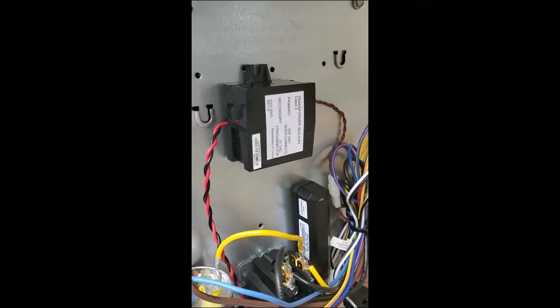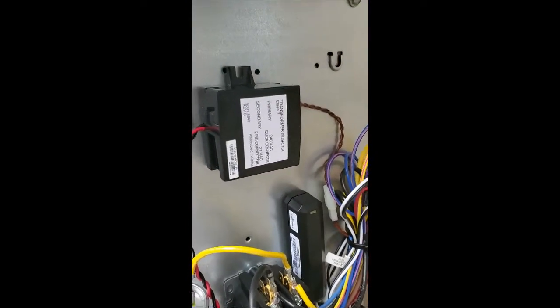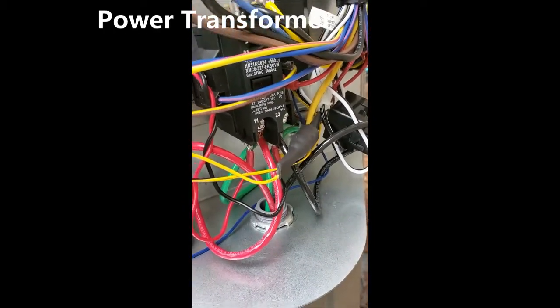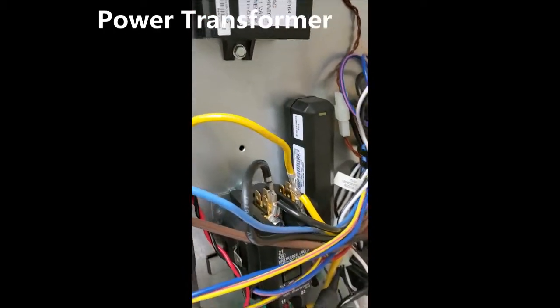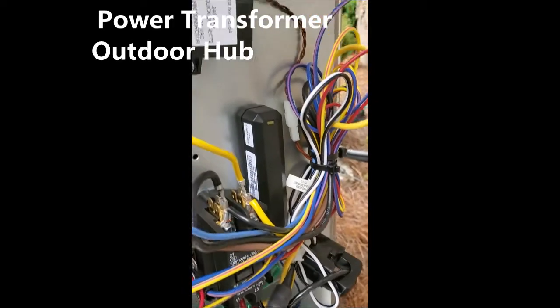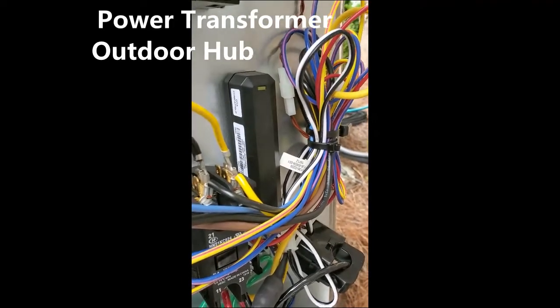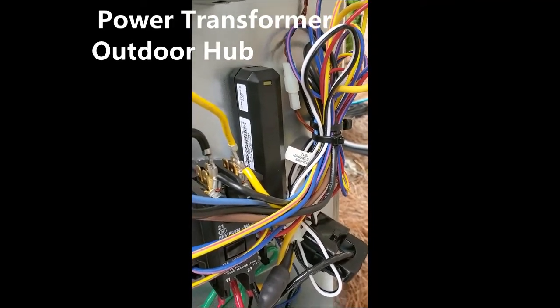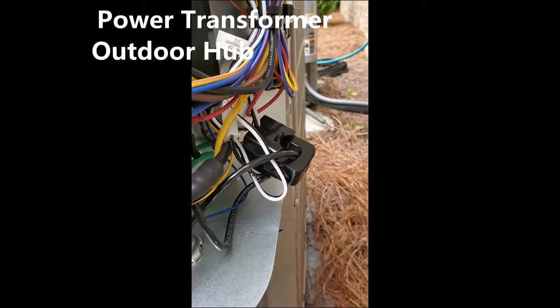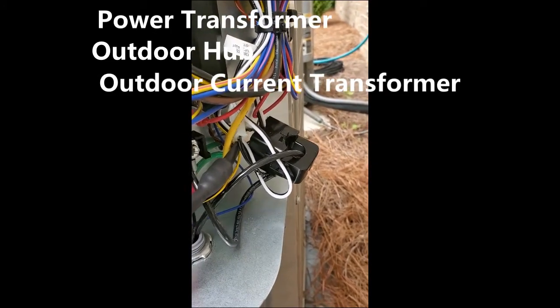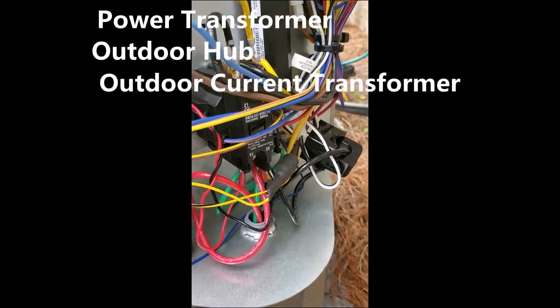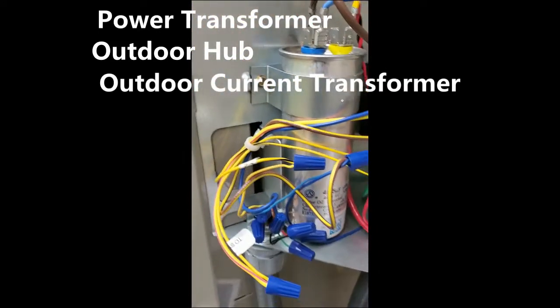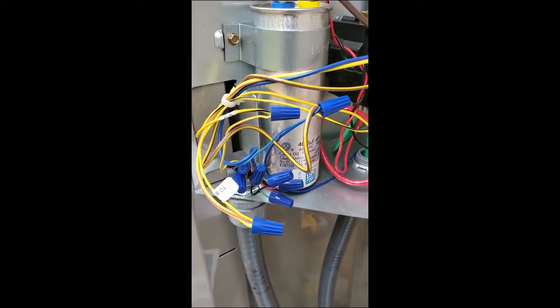So the outdoor components of the Sensi Predict includes this transformer that wires to the line side of your contactor, and that powers the Wi-Fi adapter and a couple of the other controls here. There is a Wi-Fi adapter that lets it talk to the cloud and lets you know what the outdoor unit's doing. There's a current transformer that tells you that your compressor is actually doing work and you don't have, like, a tripped breaker. And then you've got some control wires which monitor the call for cooling.